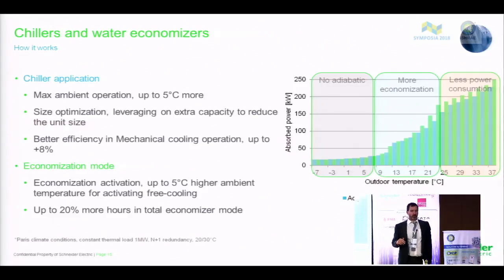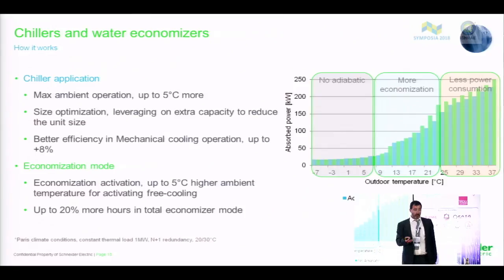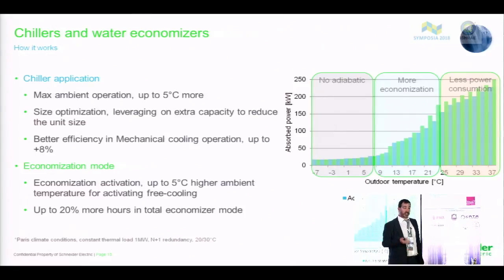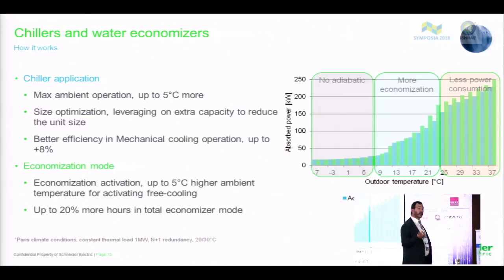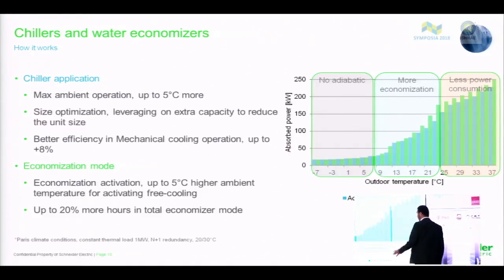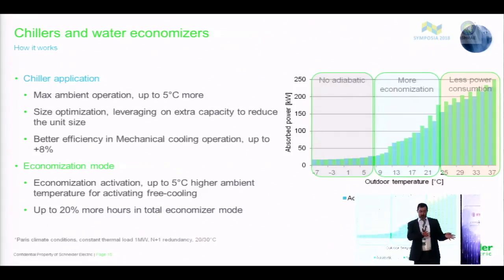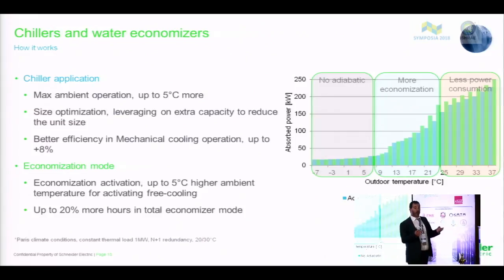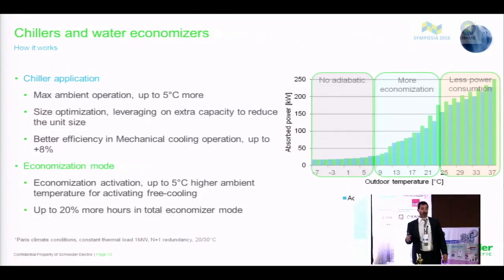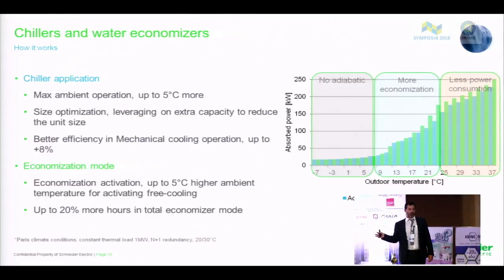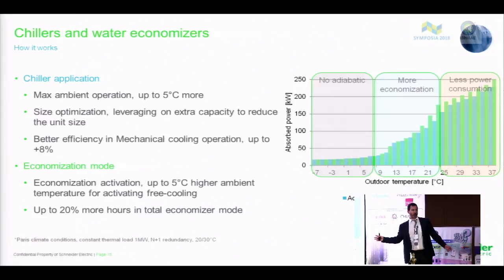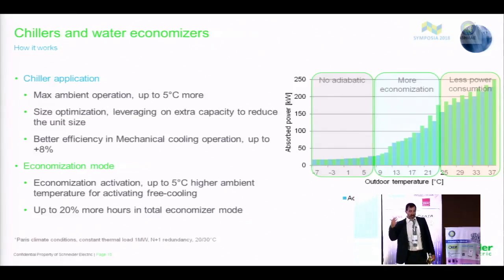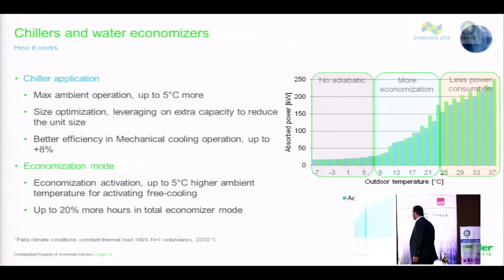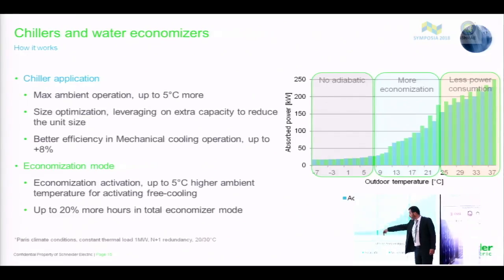If on top of that, we apply the adiabatic system, this means that the 27 is the average temperature between the wet and the dry bulb. That is probably something around 35. So this means that if we design a 2030 water and we apply the adiabatic, the free cooling can start around 34, 33 degree ambient. So in a huge part of the operating envelope of the unit. It's something that again depends on the climatic profile, but it's something that really moves the free cooling operation on the upper part of the climatic diagram.